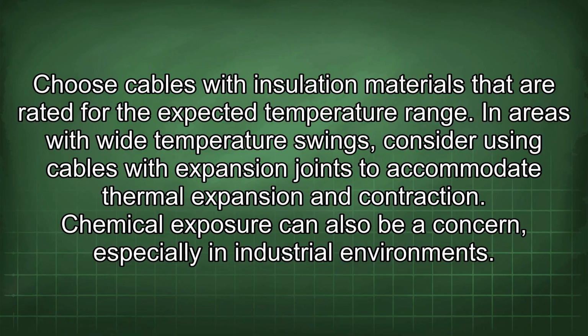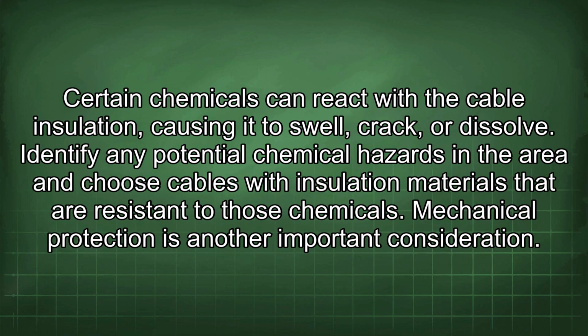Chemical exposure can also be a concern, especially in industrial environments. Certain chemicals can react with the cable insulation, causing it to swell, crack, or dissolve. Identify any potential chemical hazards in the area and choose cables with insulation materials that are resistant to those chemicals.